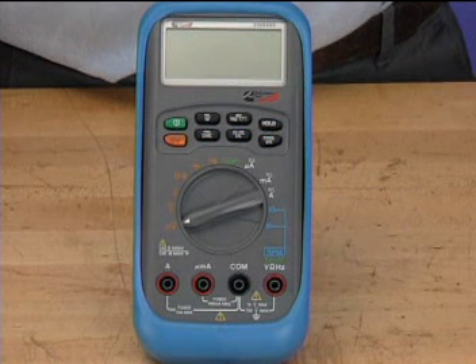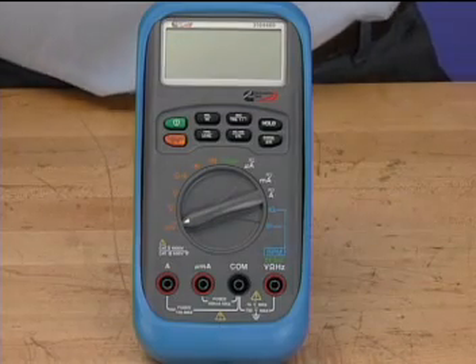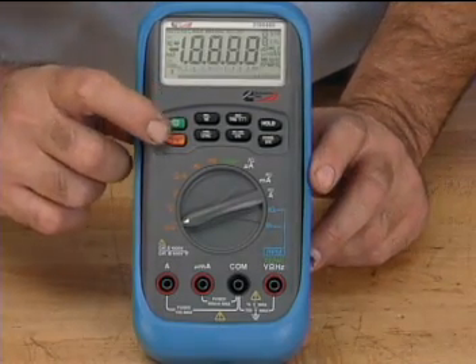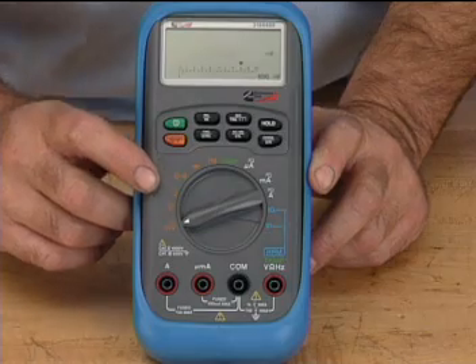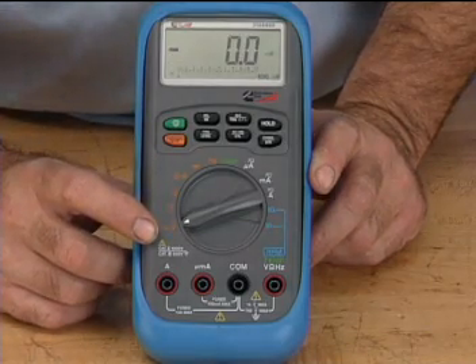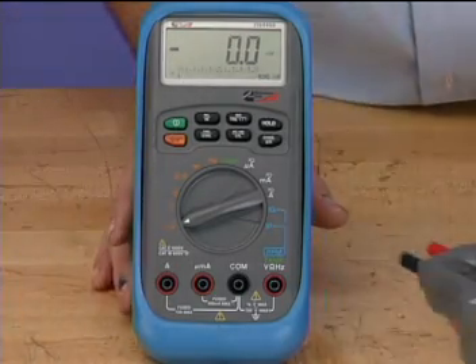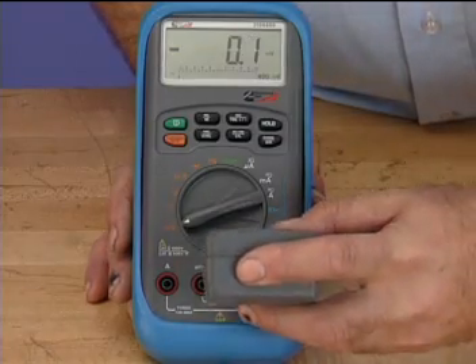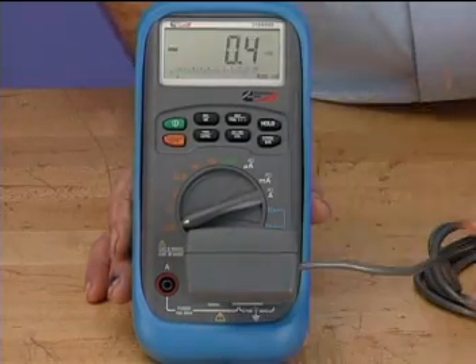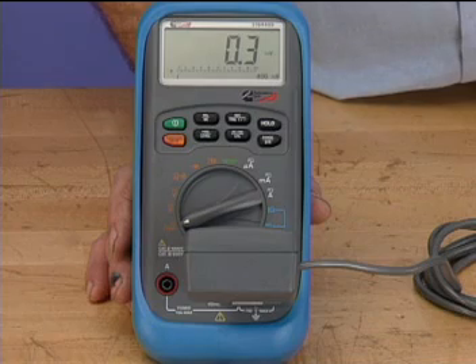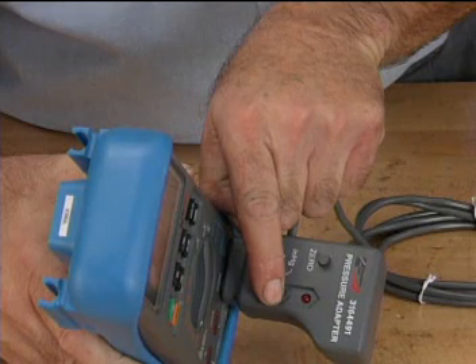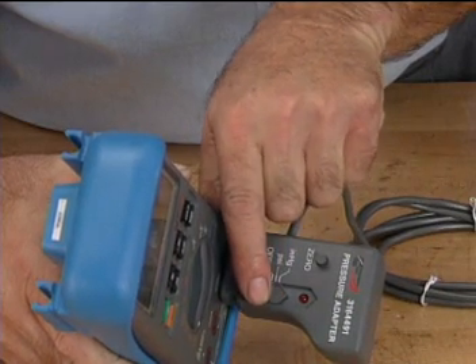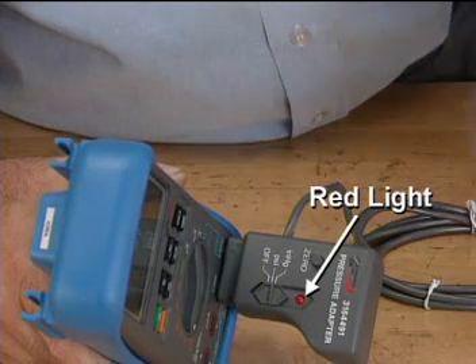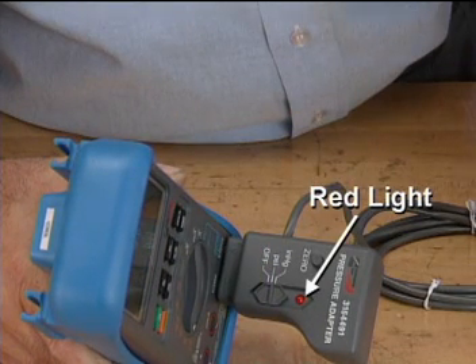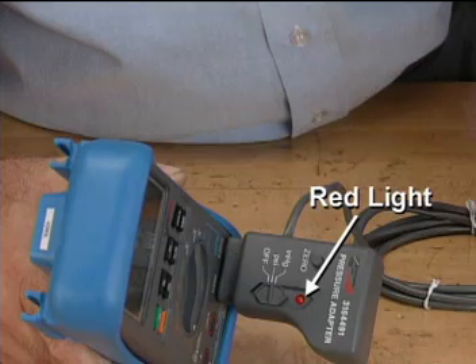Before making any checks with the digital multimeter and pressure transducer adapter, you must first zero the adapter. Begin by setting the dial on the digital multimeter to the millivolt scale. Plug the meter into the adapter, aligning the red lead with the appropriate port on the multimeter. Turn the pressure transducer adapter on and check to make sure the red light is lit. This is your indication that the battery in the transducer is good.